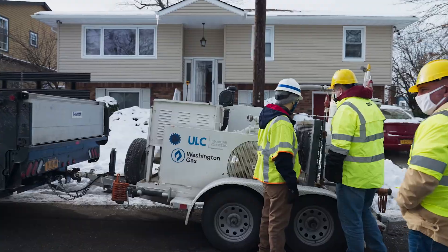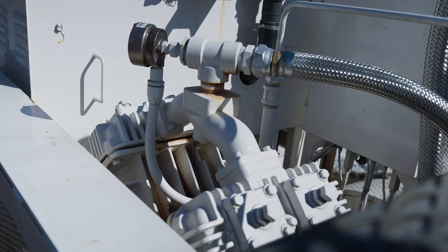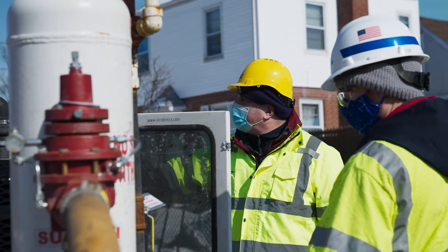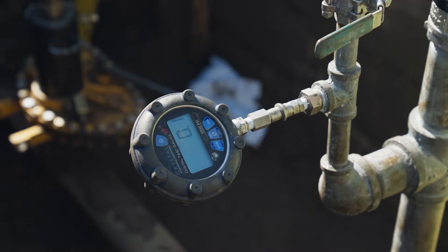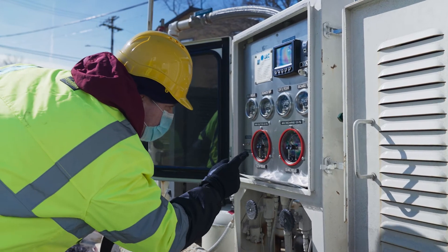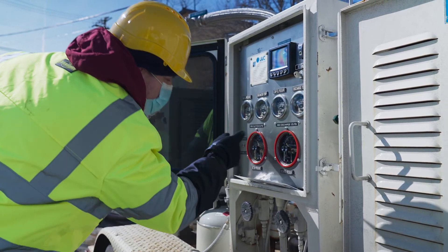Designed to meet the needs of natural gas distribution utilities, this innovative technology can take a pipeline operating at up to 300 psi and draw it down to zero or atmosphere. A radiator integrated into the unit prevents the natural gas from reaching temperatures above 140 degrees, making the Drawdown Compressor safe to use for both metallic and PE gas mains.